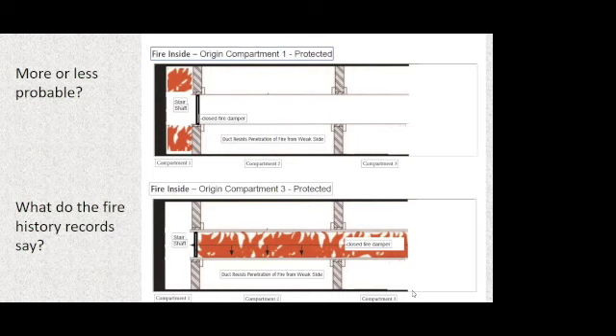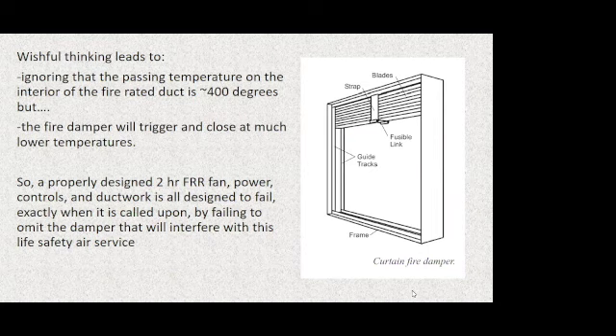And when our life safety designs for these systems, and the mistakes that are commonly made, are the source of the fire moving from one compartment to the next when it's not supposed to, it's just about the worst possible outcome that you can imagine. Designing to failure needs to stop. And we need to do that. The first step is to avoid wishful thinking. My mentor drilled this into us back in my early days. Wishful thinking is what gets you to those convenient fire scenarios instead of considering all of the fire scenarios that we're supposed to. And wishful thinking ignores fundamental facts about fire resistance. For example, that fire damper, a very, very simple device. Much like a sprinkler head, it's usually a thermal link or a thermally activated device.